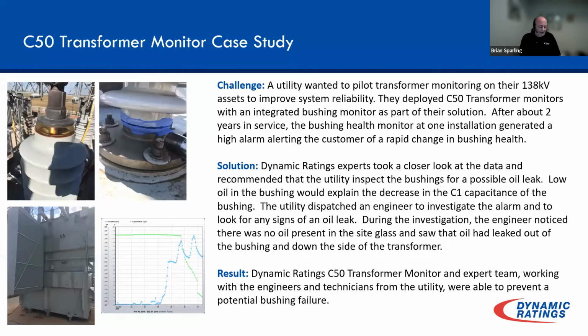It was interesting looking at the data on the failures of trying to fix leaks on transformers. Here's a case we had with one of our customers. This one was on a 138 kV distribution substation transformer, and a bushing monitor had been installed on this for 2 years prior to this event coming up, and the alarm went, and they had curious readings that the owner came to us and said, "What do you think?" Our experts looked at it and said, "Well, we think you have a leaky bushing, that the oil has leaked out of the bushing."